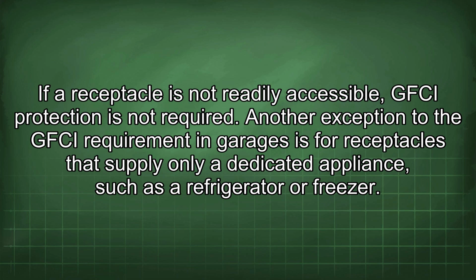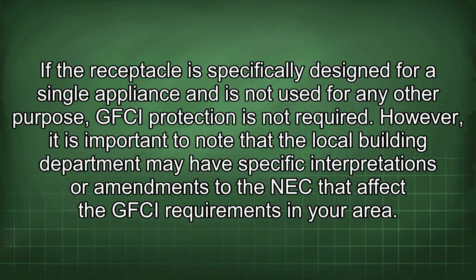Another exception to the GFCI requirement in garages is for receptacles that supply only a dedicated appliance, such as a refrigerator or freezer. If the receptacle is specifically designed for a single appliance and is not used for any other purpose, GFCI protection is not required.